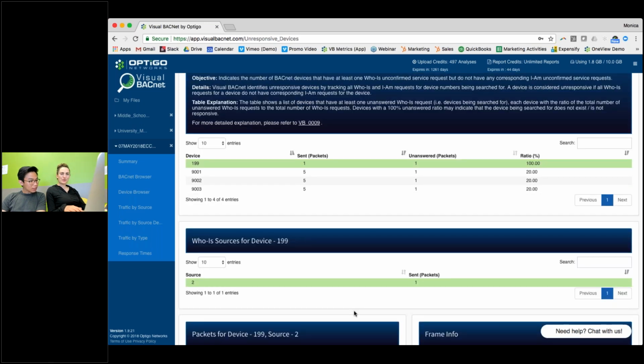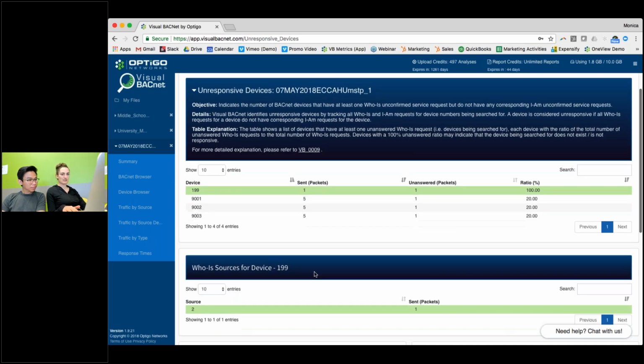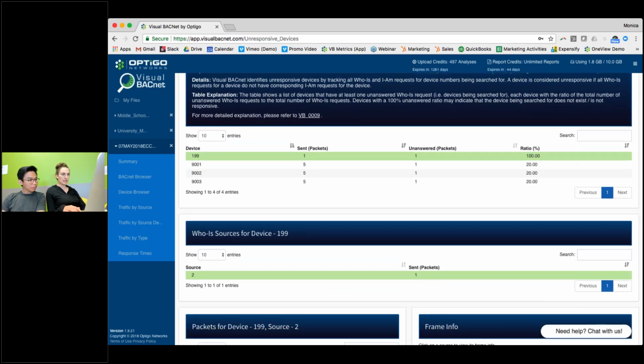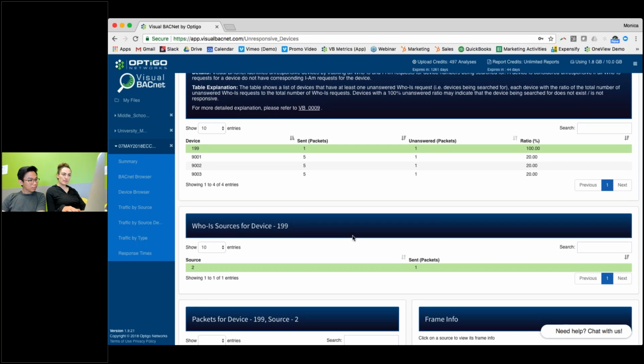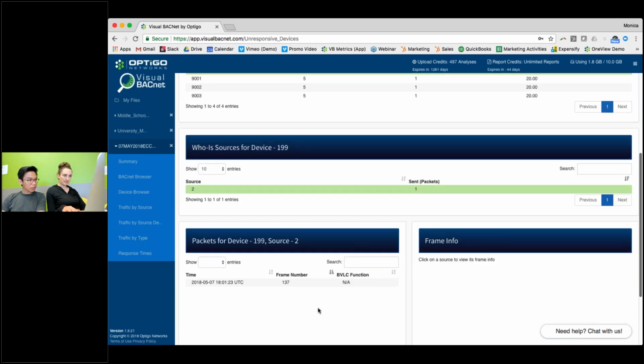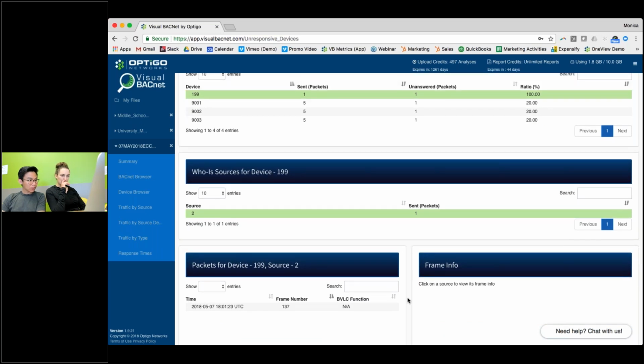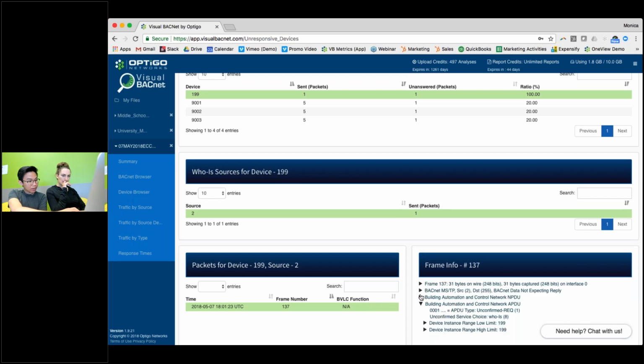Okay, sorry, let's go back. This is a 3-minute file, so quite short. But MSTP tends to show its problems pretty quickly. Only 1 packet sent. So MSTP device 2 is looking for device 199. Yeah, sent 1 packet.